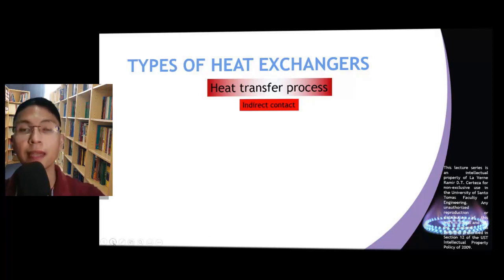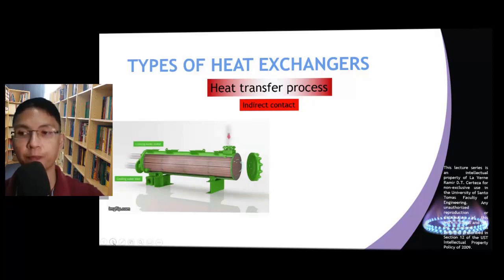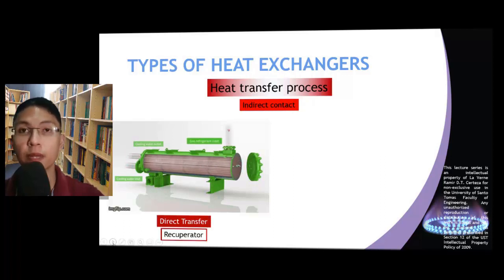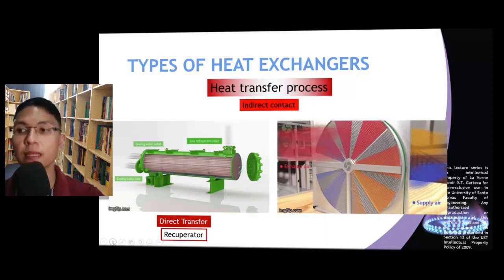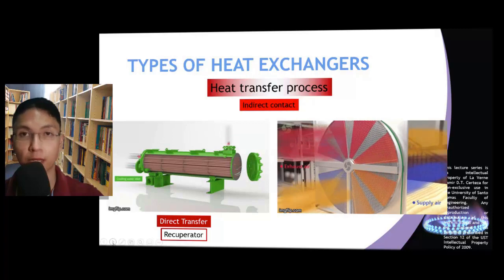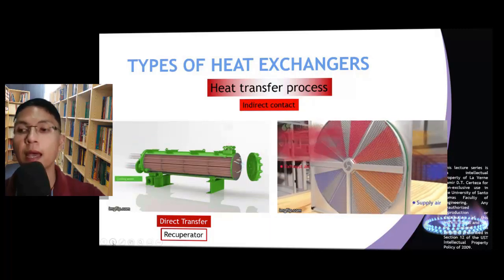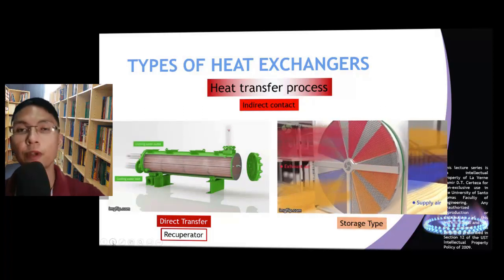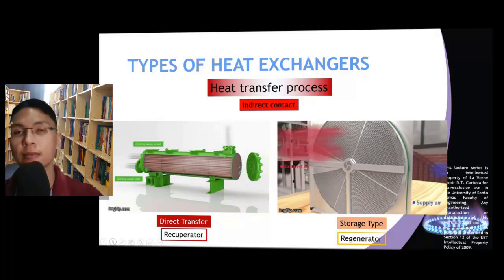Now let us discuss indirect contact heat exchangers. There are two main types under this category. The most common are those in which a primary surface exists between the heat exchanger fluids, such as the shell and tube heat exchanger. We refer to these as direct heat transfer exchangers or simply recuperators. On the other hand, some indirect contact heat exchangers involve intermittent heat exchange through a high heat capacity matrix, achieved by heat storage in the matrix and its subsequent release. An example is the rotary wheel. We refer to these as storage type heat exchangers or simply regenerators.